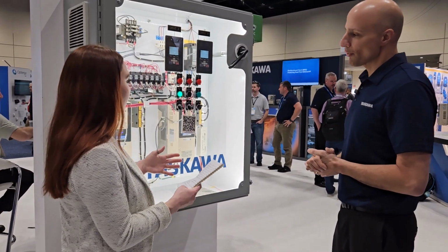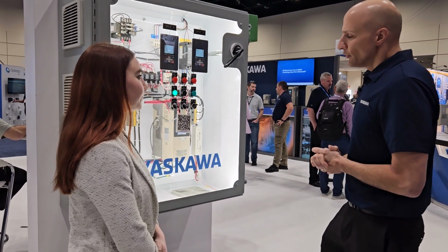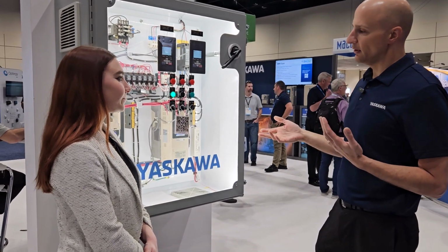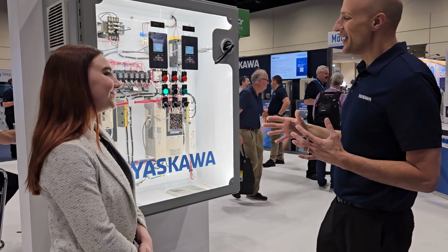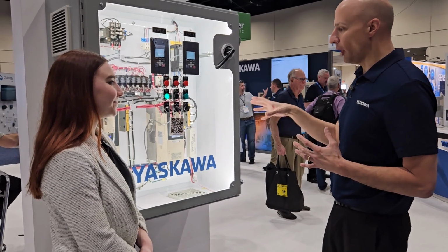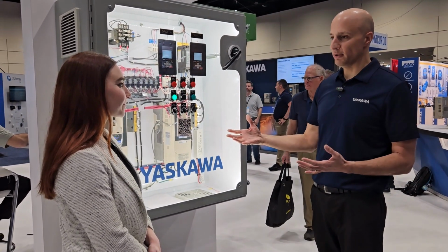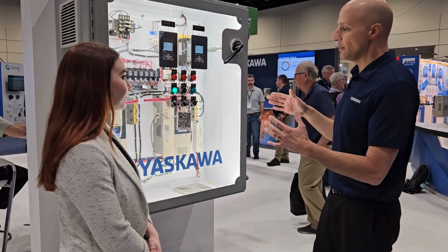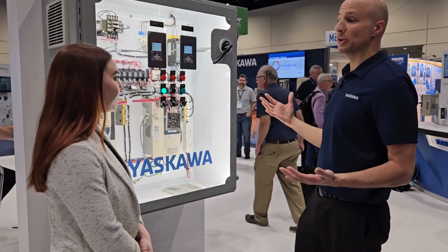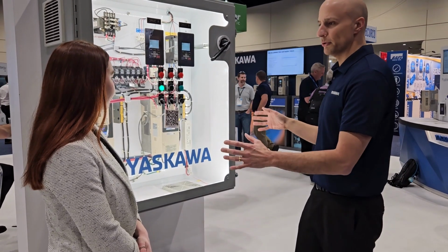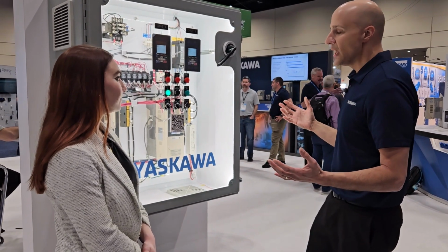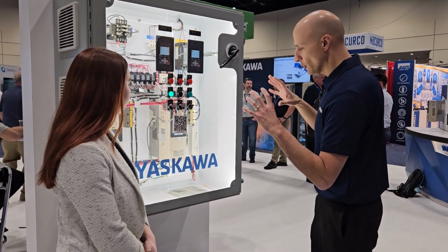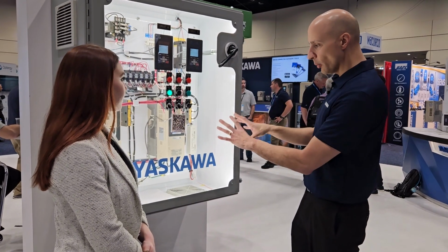And so what are some popular options for these kinds of drives? So one of the most popular options, and I work on the HVAC quoting team, and when we quote a redundant package, oftentimes it'll incorporate a fan array. And that would be the ability to power multiple motors. So maybe 6, 8, maybe even up to 10 motors. And we could have these drives be 100 horsepower, 200 horsepower potentially. And so we have one package unit with the individual motor overload relays incorporated into the cabinet.